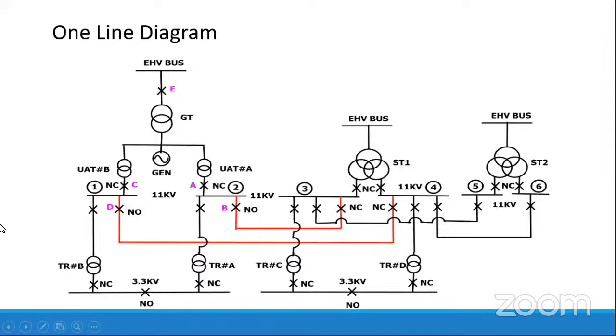Now let's come to this location. Normally there is a scheme of two incomers and one bus coupler. In normal condition, the bus coupler will remain open and the incomer feeders will be in line. You can see here the NO indicates normally open. So the bus coupler at 3.3 kV will be normally open, and the two incomers from transformer B and transformer A will be feeding power to the network. If any of these incomer feeders gets isolated due to maintenance, or if a fault occurs, then this incomer feeder will open, and the bus coupler will close, such that the continuity of the power will be there. There is no interruption of the power supply.